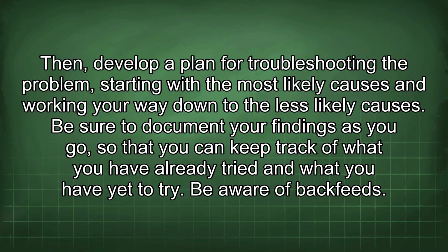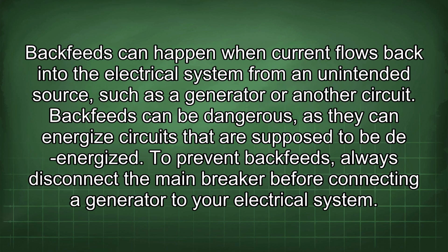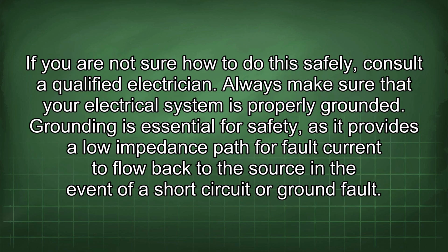Be aware of backfeeds. Backfeeds can happen when current flows back into the electrical system from an unintended source, such as a generator or another circuit. Backfeeds can be dangerous, as they can energize circuits that are supposed to be de-energized. To prevent backfeeds, always disconnect the main breaker before connecting a generator to your electrical system. If you are not sure how to do this safely, consult a qualified electrician.